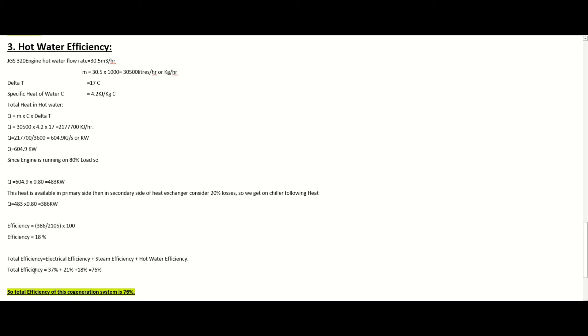Now summing up all efficiencies: electrical efficiency is 37 percent, steam efficiency is 21 percent, and hot water efficiency is 18 percent. So the total efficiency of the cogeneration system is 76 percent. In this video I have used the parameters from my own system. In your case you can put your own parameters for your gas generator to calculate your cogeneration system efficiency very easily. I hope you liked this video — if so, please share your comments and subscribe to my channel. Thank you very much.